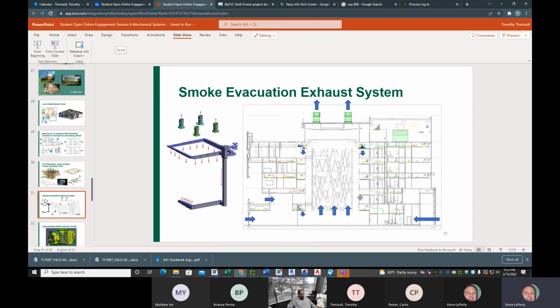Now, we're delivering less air than we're exhausting, and the reason for that is once these big fans turn on, the windows open up, the doors open up, and other openings from outside bring in a large amount of outside air to come and deliver itself up and out of the building through these four giant smoke evac fans that we have. They have a fan that'll turn on that's separate from the air handler system, and that'll deliver the air down as well. So if I remember the numbers correctly, I think this delivers 80,000 CFM, and the four fans are exhausting 270,000 CFM.